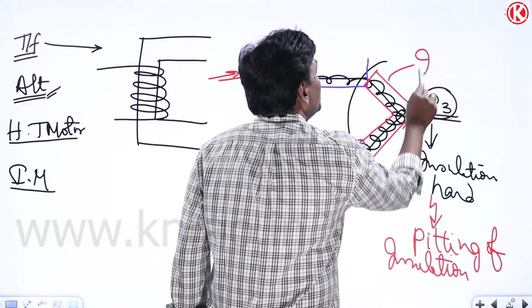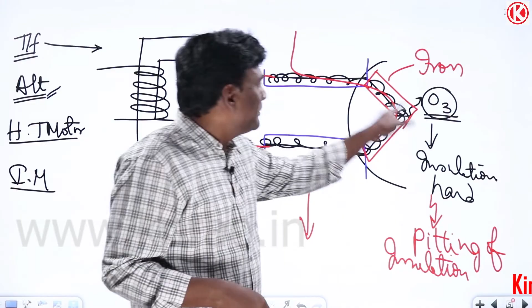No, because if I use iron boxes to support the back-to-back connection mechanically, my field flux will go through this, because that is iron. But intentionally, at any cost, back-to-back connection should not have any flux. So what has to be done? Rather than iron, use aluminum boxes. So interview question here is, why back-to-back connection of an alternator will be supported by aluminum boxes?